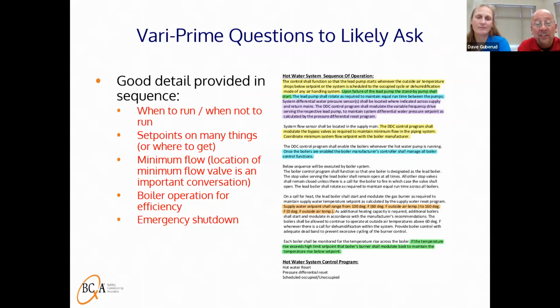And then the emergency shut-off switch. Depending on the size of your boiler system, they are required by code. Code actually indicates that these boiler switches should be located outside of the boiler room, but leaves an exception, or variance, that they can be located immediately inside the door if it's kind of like a public corridor. But still, as a courtesy, you really should be making your AHJ aware of this, because they're the ones that are still the final judge on where that goes.